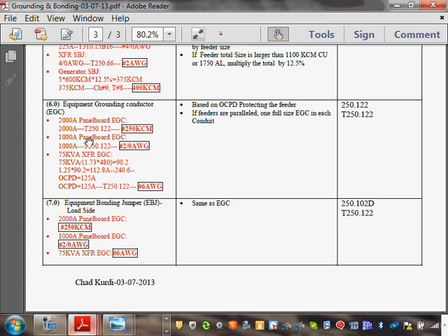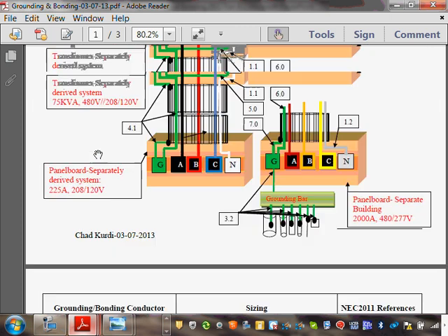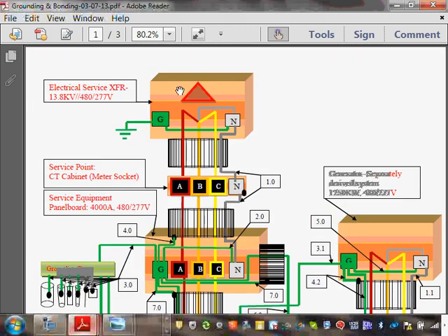Now let's dig a little bit deeper, and if you don't mind, you just sit here. I'm going to walk you through it, and I wish I could be in a different situation. So let's start from the beginning for grounding and bonding. So here's your transformer. Remember we said there is a decision that you have to make when you have a transformer. Are you running a grounded system, impedance grounded system, or solidly grounded system? Very clear. There is no impedance here, and I'm tying the neutral. Can you see the neutral at the transformer, which is part of the winding? I'm tying it to Mother Earth. So I'm running a solidly grounded system.